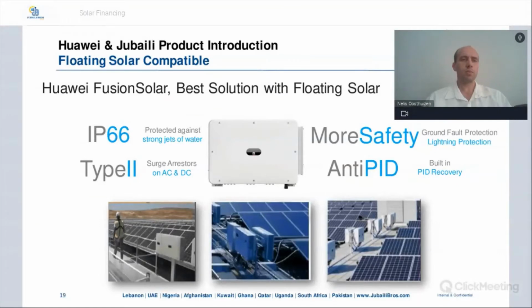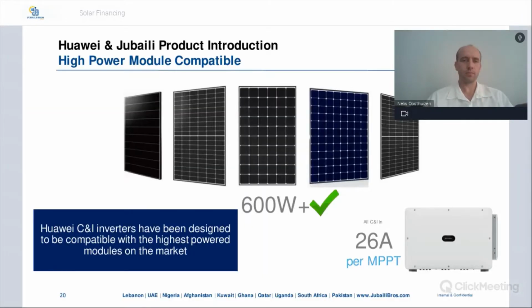Then Huawei inverters are also compatible with floating solar PV applications. The inverters are rated IP66. They've got built-in Type 2 surge arresters on both AC and DC side. Anti-PID is also built into the inverters, and there's more safety with ground fault protection and lightning protection. Then Huawei inverters are compatible with high power PV modules. Lately, with the bigger range of PV modules, the 550s, or as soon as you go 595, 600, the short circuit current rating of these modules is typically a lot higher. But on the Huawei inverter, the MPPT can handle 26 amps, so it is compatible with high powered modules.